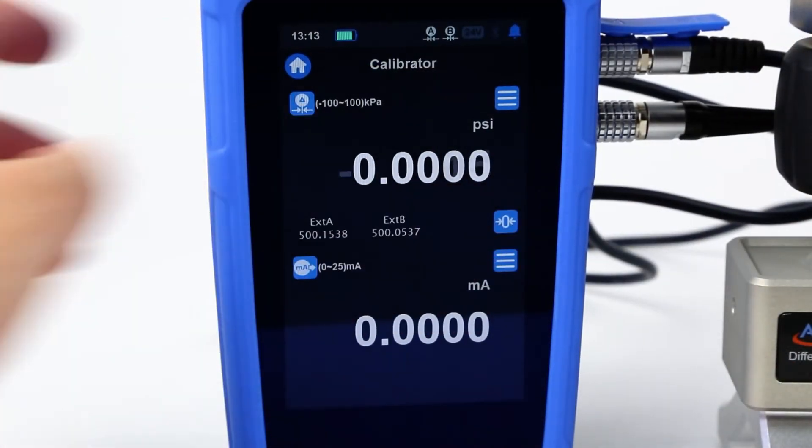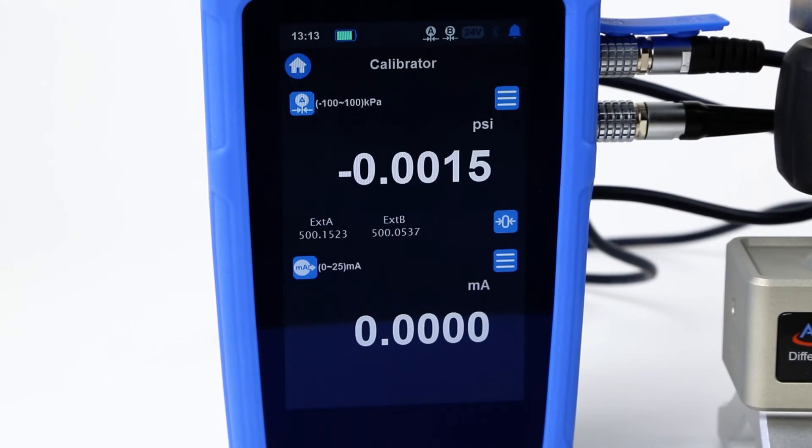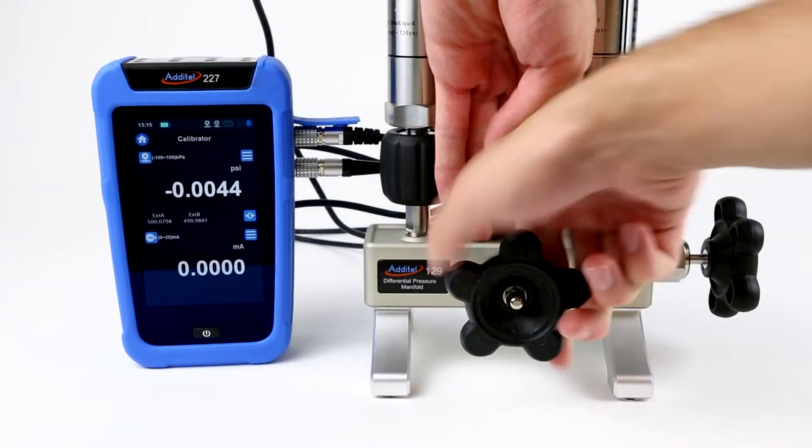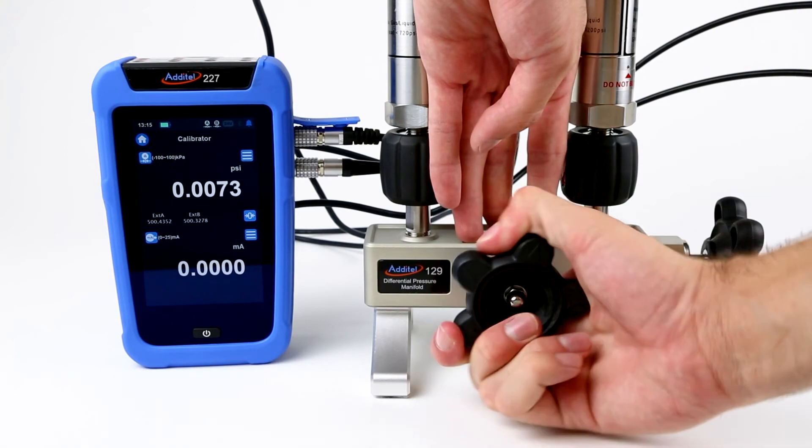Now we zero both pressure modules at the static pressure, which happens to be 500 psi in this case. Now that we are zeroed, we will isolate the low pressure port from the high.